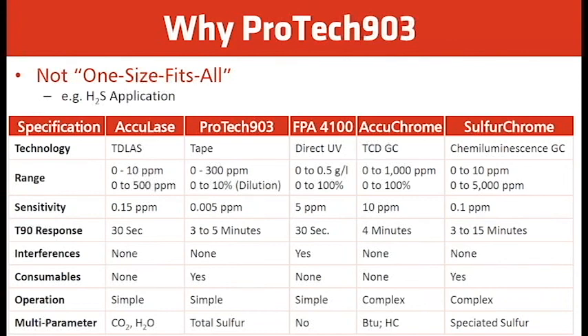The SulfurChrome is a chemiluminescence-based GC that can speciate all sulfur compounds. For H2S, it can do 0 to 10 ppm up to 5000 ppm, with sensitivity of 0.1 ppm and T90 response of 3 to 15 minutes depending on the application — for H2S only it could be under two minutes. No interference, consumables yes, operation is complex.